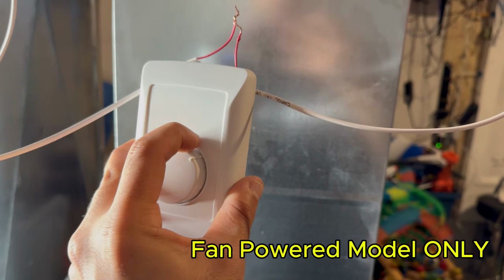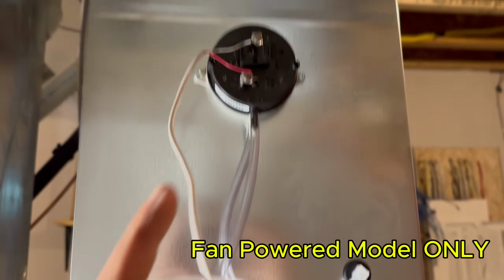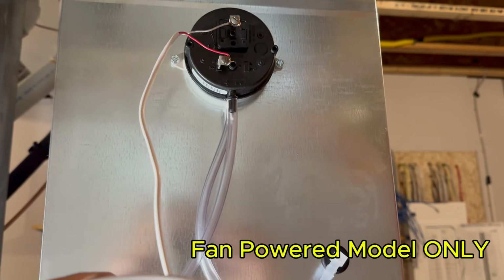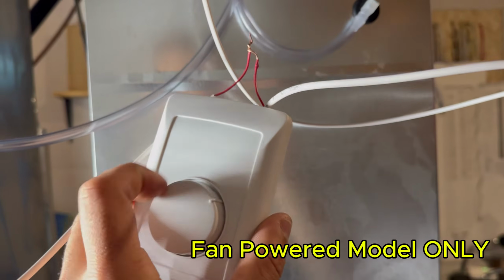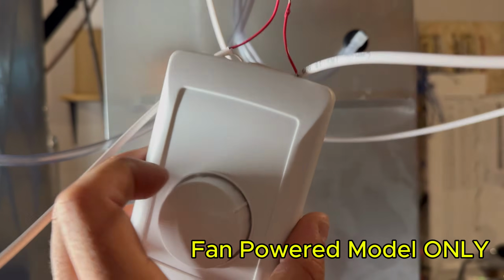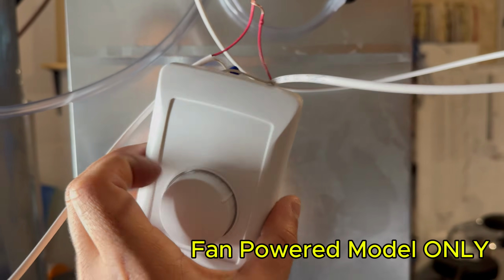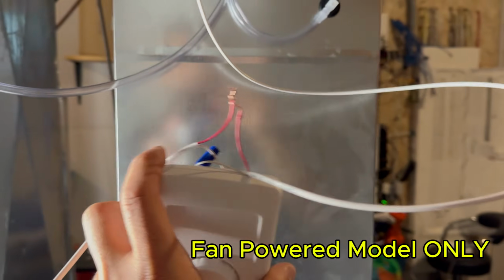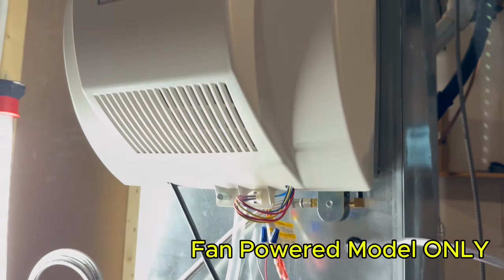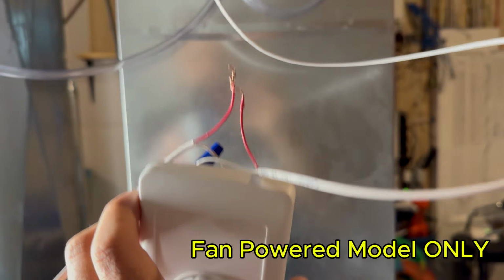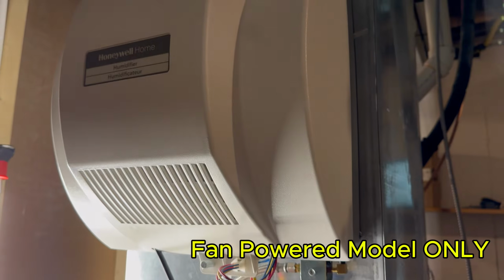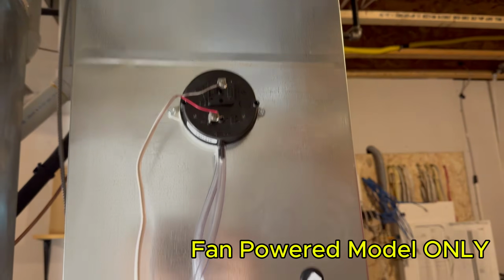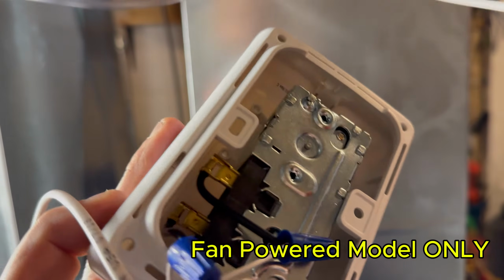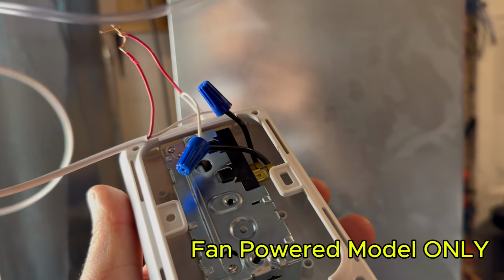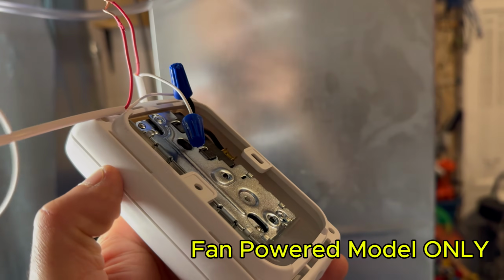Now, once you set your humidity, if there is vacuum and this pressure switch is telling the system you can now turn on, this will allow you to turn on the unit using this analog humidistat. So let's recap one more time. You're going to have the two red wires coming from the humidifier and the pressure switch connected together at the humidistat. And then you'll have a white wire from the humidifier and a white wire from the pressure switch, each of them connected to the black wire on the humidistat. And that's it. It's as simple as that.